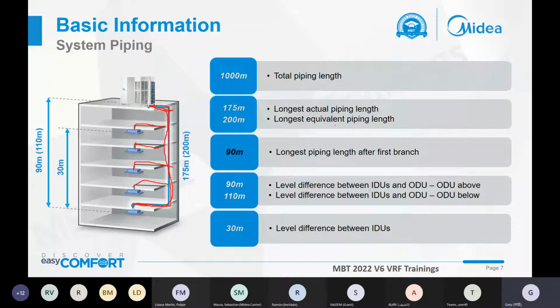So what is the longest equivalent piping length? Actually, when we calculate the actual piping length, we don't consider the branch pipes. But in the longest equivalent piping length, we should consider the branch pipes. Normally, we can think each branch pipe is equal to 0.5 meter. So this is why we have the two measures, and the longest equivalent piping length is bigger than the actual piping length.